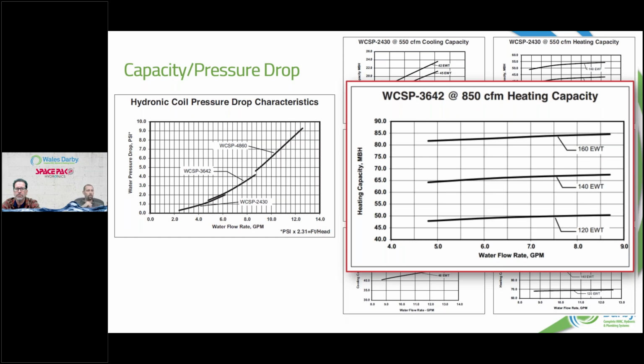You can see anywhere from 50 all the way up to maybe 67,000 BTUs, all the way up to just about 85,000 BTUs, right? So that's the one air handler, the 3.5 ton system, but based on the water temp and the GPM, we can increase those BTUs getting out into the space. So I think that's what's pretty cool about the air and water stuff, is we have that flexibility. You're not just stuck and married to the source and the emitter. We can play around with water temps, GPM, and all this other stuff and tailor the BTUs we need to get to that space.